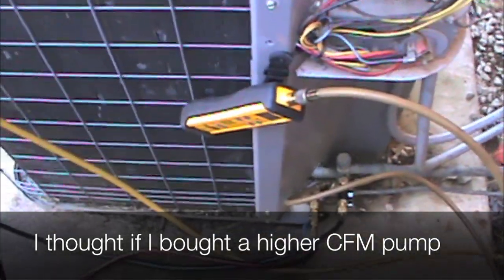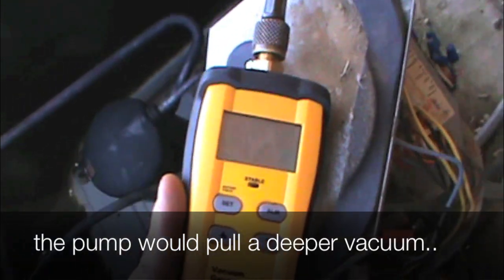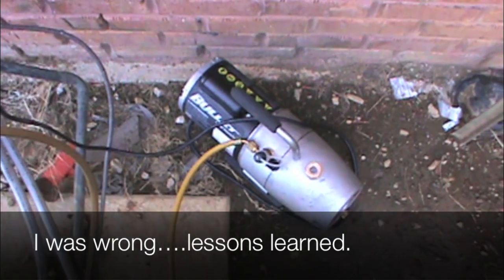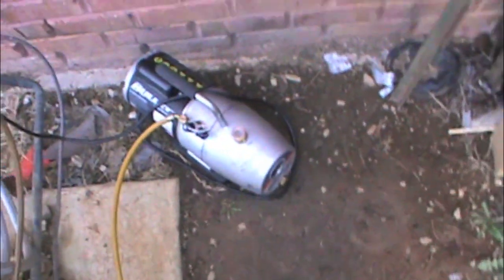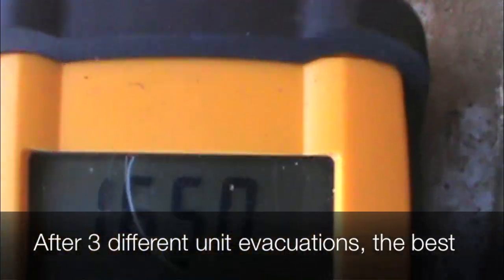All right, we are out here. We got our pump on it. We got a new pump. This one's not near as good as the one I have though — you can tell by how deep the vacuum goes. The other one was rated a six, they say this one's a seven. I don't believe it. We're still coming down now.